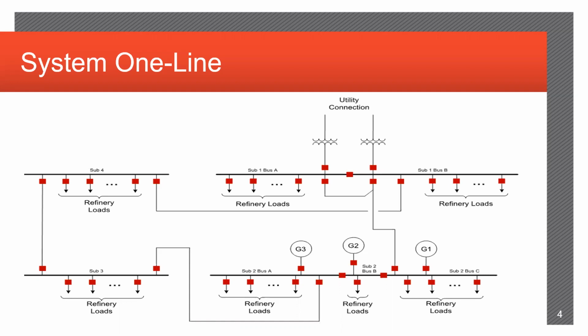As I said earlier, this has to happen relatively quickly, because if the island isn't detected quickly enough, the generators can drift in frequency. They have an upper bound and a lower bound, but depending on how big the load mismatch is at the time of islanding, you may go over frequency or under frequency pretty quickly. So we needed to detect it fast in order to send the signal to the generator control systems to change mode and catch the rest of the system before the generators tripped off on under frequency or over frequency. But unfortunately, I don't have a good number for you. I don't know how fast it happened in the implementation.